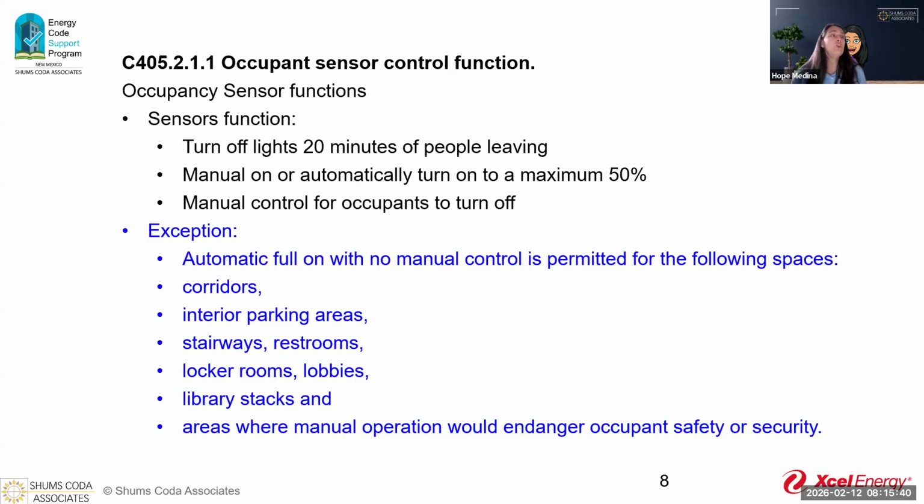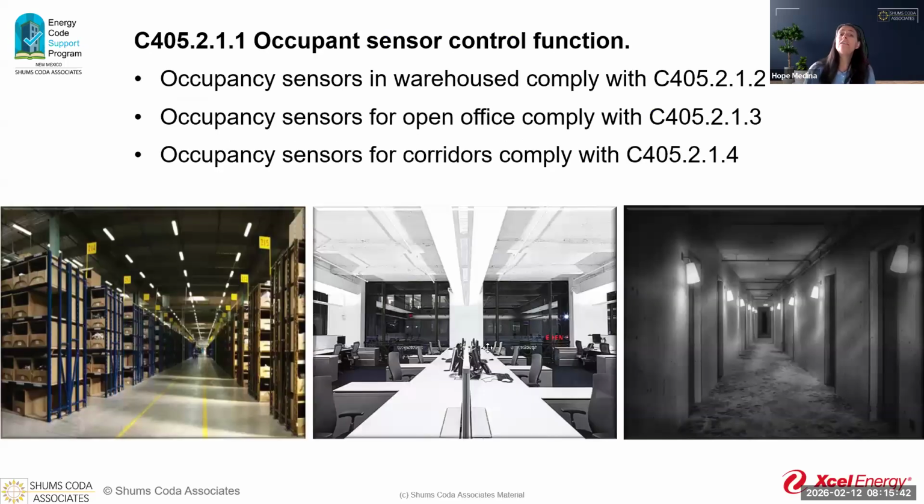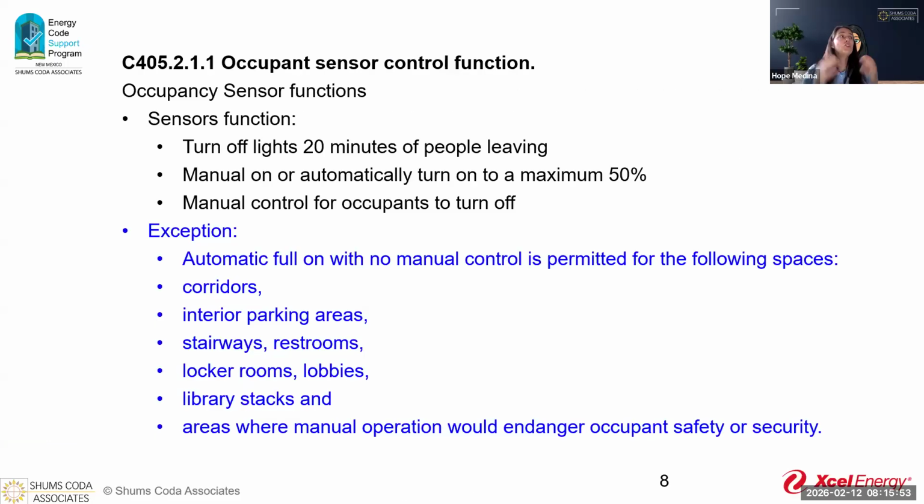If you are not one of these three, where we're going to do specific sections with very specific criteria to that use of space, and it's just, I need to install an occupancy sensor because I'm a classroom, now what we have to do is have a sensor that turns off the lights 20 minutes after everybody has left the space. So this would typically be a vacancy sensor concept.